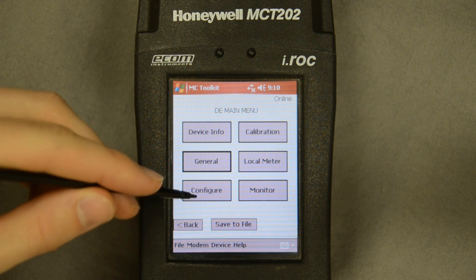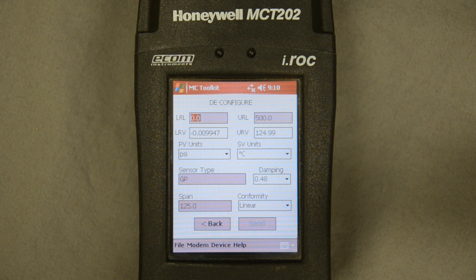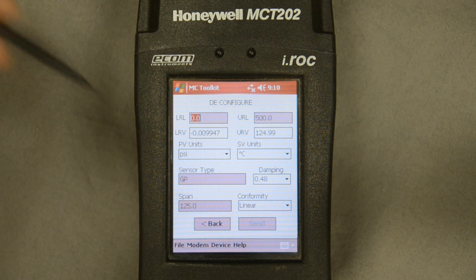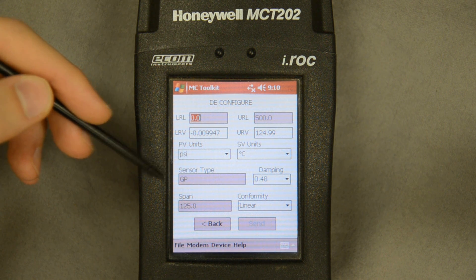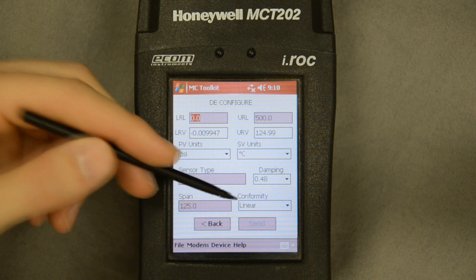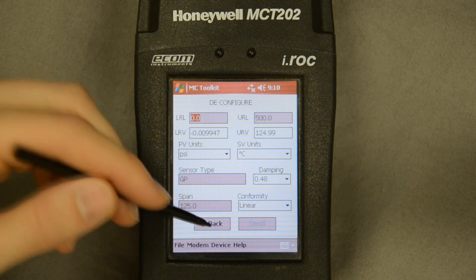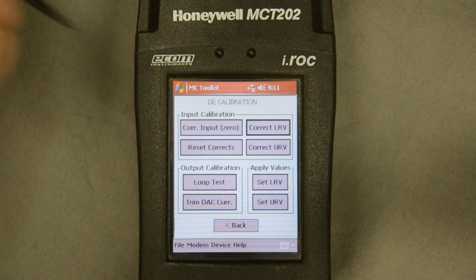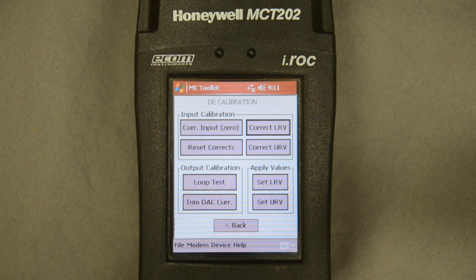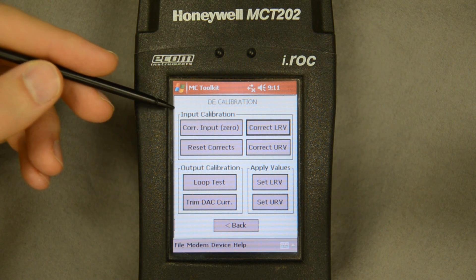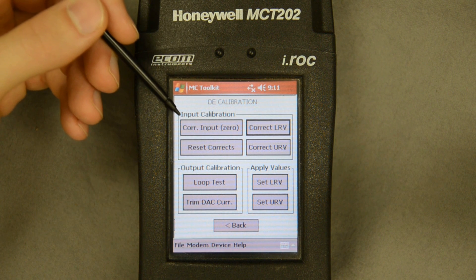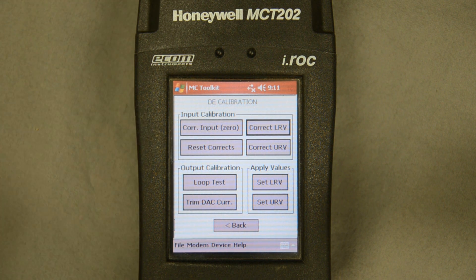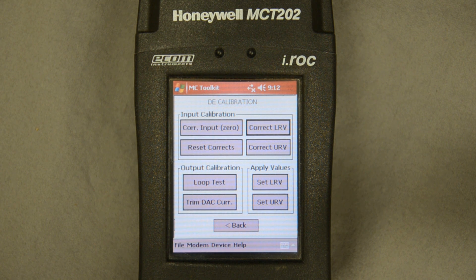Just like with the HART device, here I can configure the transmitter. I see the upper range limits in PSIG — this is a gauge transmitter. I see the level of dampening and the conformity, all configurable on this screen. In the calibration screen I can make changes to the output — for instance a slight sensor adjustment, corrections to the lower range value or the zero. I can also do the loop test here and reset any corrections I've just made.